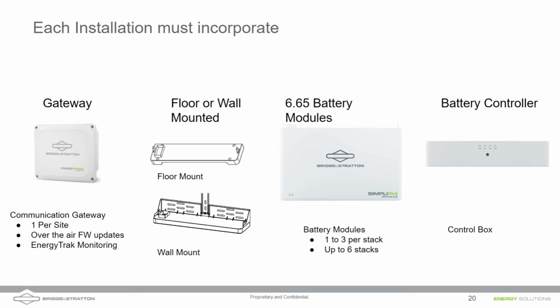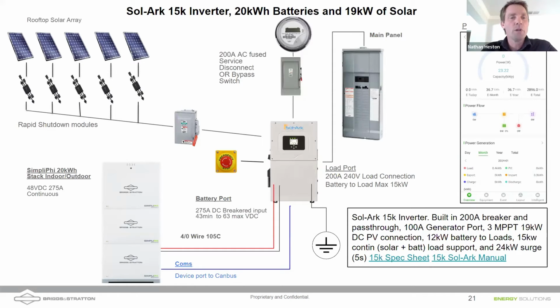John, let's jump into looking at a single line diagram here for a Sol-Ark 15k. This is a basic example in which we've got a single stack of 3 of these 6.6 batteries to get 20 kilowatt hours. This is a DC coupled example. We've got rapid shutdowns to be compliant for a roof mount array. We're coming through a disconnect that, of course, doesn't have to be a fuse. That could be a breaker disconnect, as John was saying, is the most economical way to disconnect.